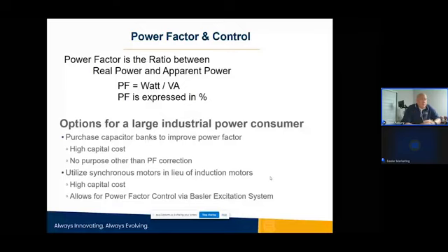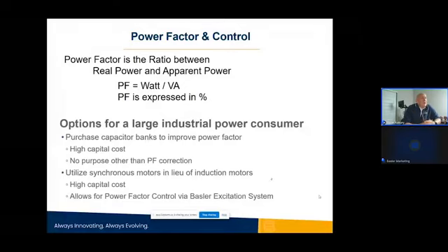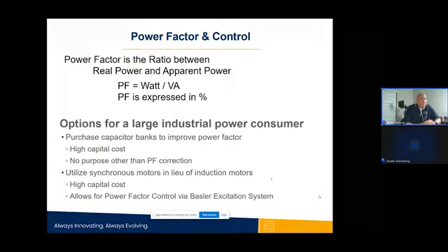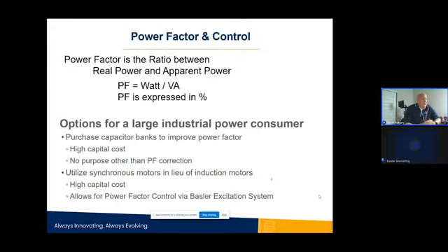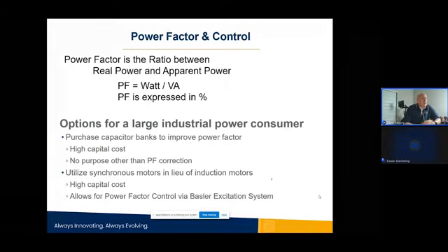Options for large industrial power consumers that maybe have poor power factor at their plants, and may even get penalized for it: they've got a couple options. They can purchase capacitor banks. They're pretty expensive, and the only purpose is to give you power factor correction. But for some applications where a synchronous motor makes sense, where you've got a slow speed machine and you really don't want to put an induction motor out there because of the efficiency issues, utilizing the synchronous motor can perform the work that you need done, but it also can give you that power factor correction through an excitation system that can regulate that power factor.